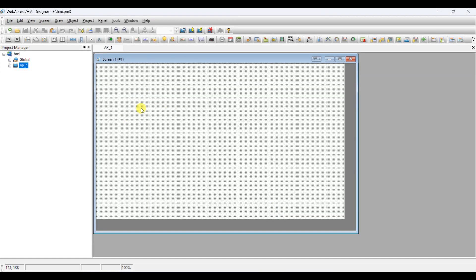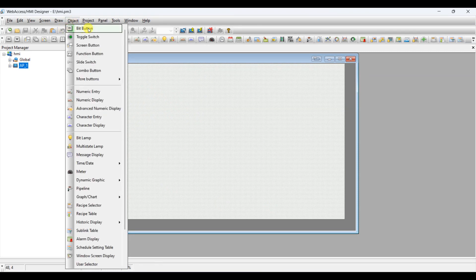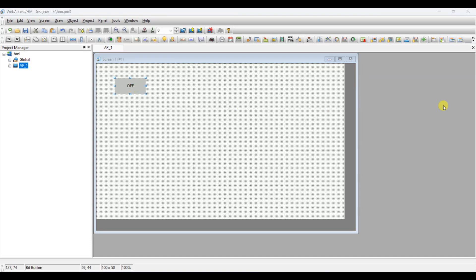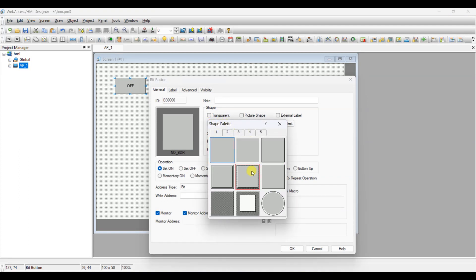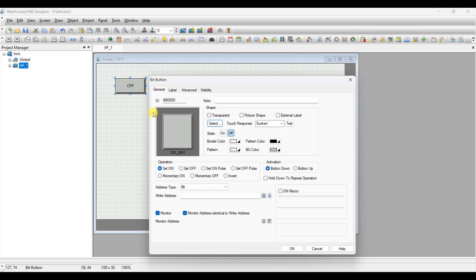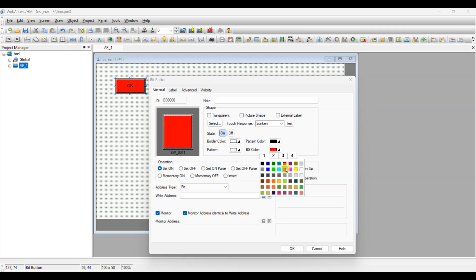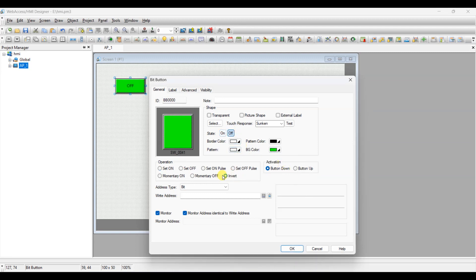Here we are seeing a blank HMI screen — let's design it. From the object menu, select bit button. Double click on it. Select the required shape by clicking on the select button. Select the color for the off state of the button from BG color as green. Similarly, select the color for the on state of the button from BG color as red. Select the invert option — you have to select the invert option, else HMI will not properly turn the memory bit on or off. Enter the address of memory bit M0, that is 2049.